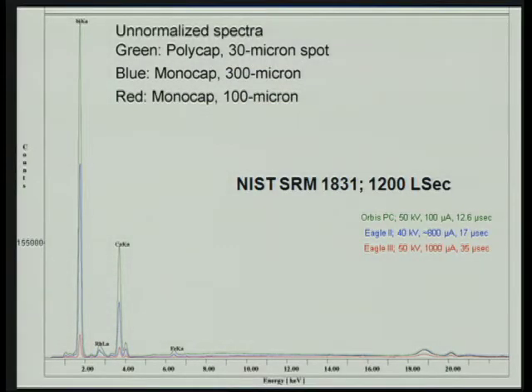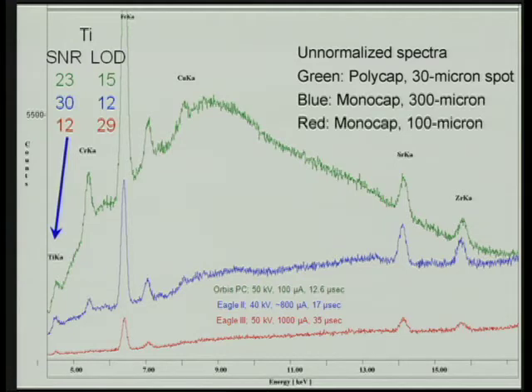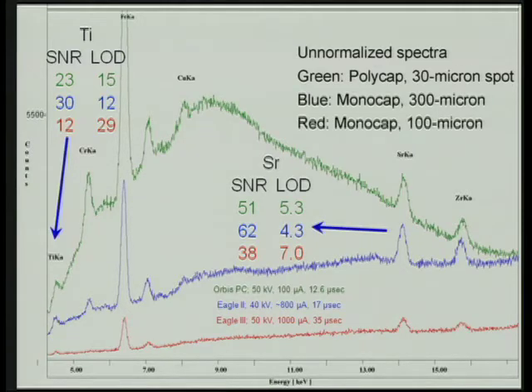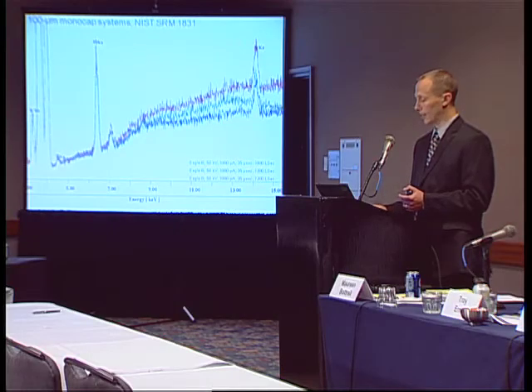Here are unnormalized spectra from those three systems — SRM 1831 for 1200 live seconds. You can see the poly-cap has a lot more signal than the other two, and the 100 micron mono-cap has significantly less. Expanding to that region, you see the same increased intensity and also increased background. To compare these systems, you look at their LODs — here are titanium's signal-to-noise ratios and LODs for those spectra, then for strontium. The next slide shows three very similar 100 micron mono-cap systems where the only difference is the green trace was collected for 1800 live seconds instead of 1200. The LODs for titanium and strontium are fairly similar from one system to another, as you would expect.